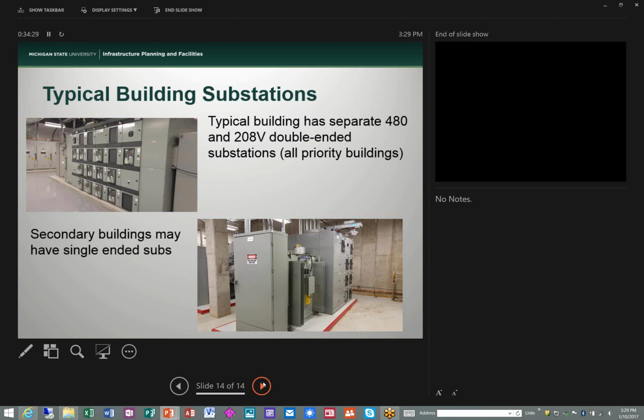We have a few of the smaller buildings where we've sub-fed a building from an adjacent building where the load is that small, Mike. All of the subs have liquid transformers, no dry type transformers on the utility subs in the buildings. And obviously we try not to load each transformer past 50%. There's one building in particular I can think of, the HANA administration building, the 480 sub. We're a little heavy on the one end and at 50% on the other end. Once we get the new data center built, the compute load will move out of that building, and the cooling load will come off of that sub, so we'll be below 50%.